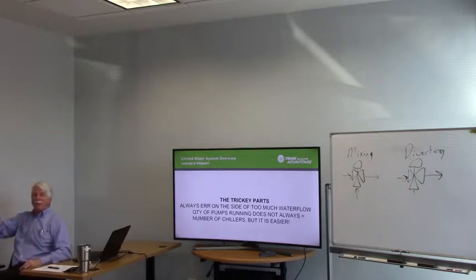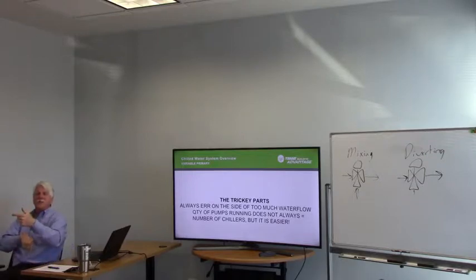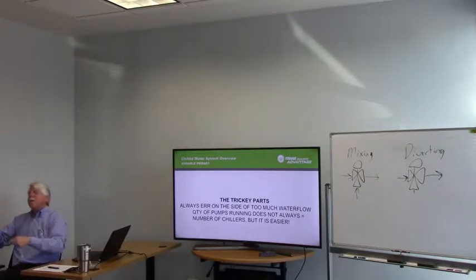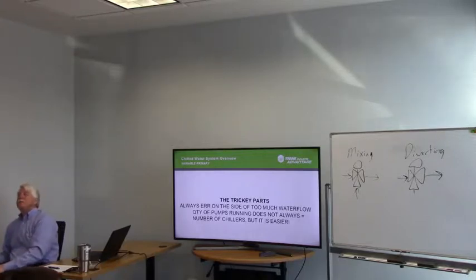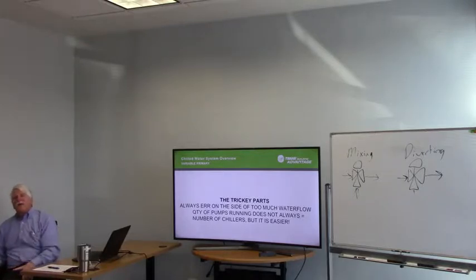We have an agreement with the service company that if we have staged pumps where we can't do that, that pump output will wire to a UC 600 as an input, and we will have standalone programming in that 600 to make sure a pump starts whenever that thing requests it. But what I want to say is, if you see a centrifugal, don't have the centrifugal control it as well. Yeah, traditionally on centrifugals, the pump output will control the valve. Correct.